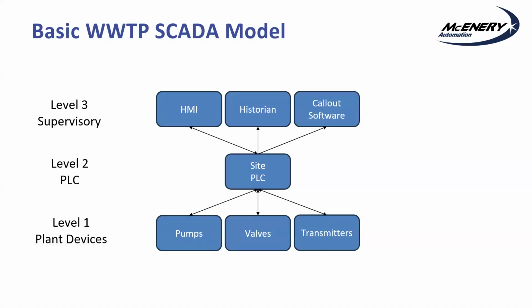For the basic layout of a SCADA model, we'll start at level 1 with the plant devices, which will be all the pumps and valves, transmitters, all the sensors that you have that gather data for your site, that you may be going out and looking at manually, or you may already have a PLC or multiple PLCs on site, but you tie all that data back into the controllers, and you may have separate, several isolated networks on site due to geographic location, whatever.